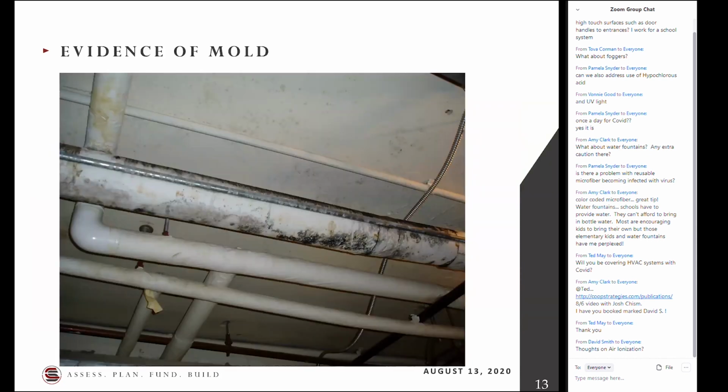What you'll see is a chilled water line for a heating and air conditioning system, above a suspended ceiling where it's really, really hot and humid. Even unless you have the perfect insulation job with everything lapped and sealed and water resistant, you're going to have a condensing surface.